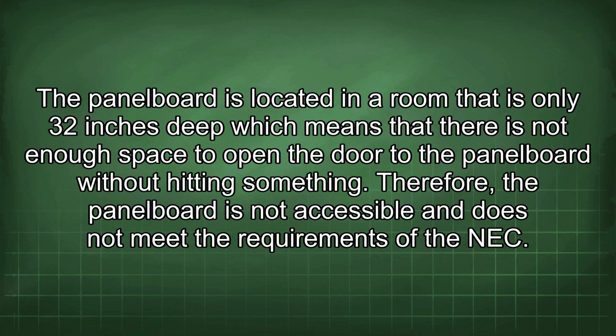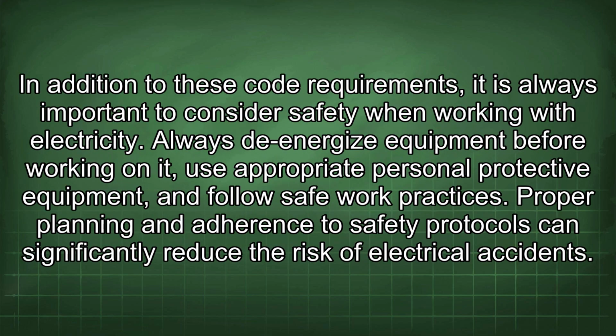The panelboard is located in a room that is only 32 inches deep, which means that there is not enough space to open the door to the panelboard without hitting something. Therefore, the panelboard is not accessible and does not meet the requirements of the NEC. In addition to these code requirements, it is always important to consider safety when working with electricity. Always de-energize equipment before working on it, use appropriate personal protective equipment, and follow safe work practices. Proper planning and adherence to safety protocols can significantly reduce the risk of electrical accidents.